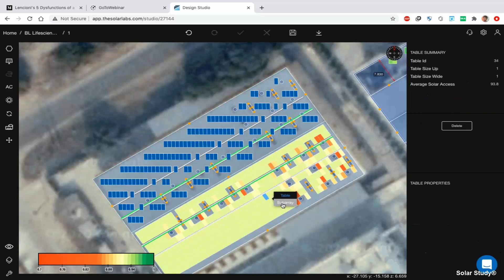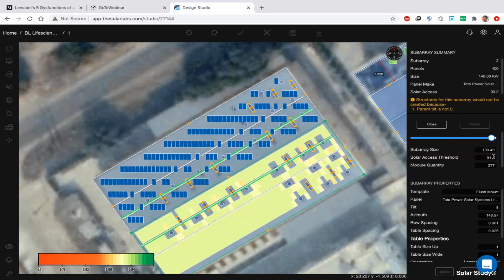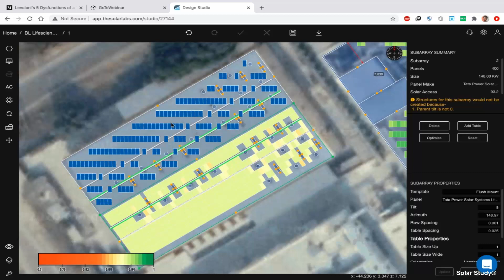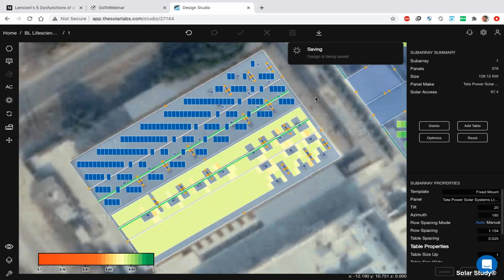And here again, we see that solar access is not green anymore as it was in the RCC shed. This is because the tilt is not optimum. So instead of 20 degrees tilt, it is at 8 degrees tilt. The second factor is instead of 180 degree azimuth, it is at a tilt towards east. So that is reducing the overall solar access potential. So here we can see that, on average, we'll receive around 91.1% of total solar energy as opposed to around 97.4 here. So by virtue of laying out panels in this configuration versus the RCC, there is a drop of around 6% in generation. So yeah, I'm just going to save it quickly and move on to show you the report.